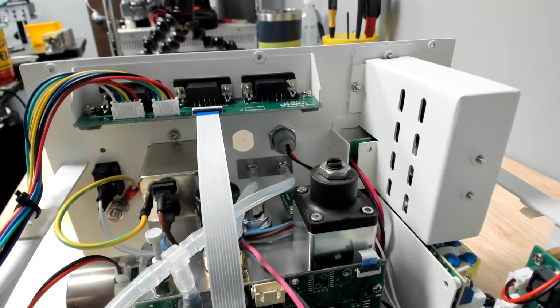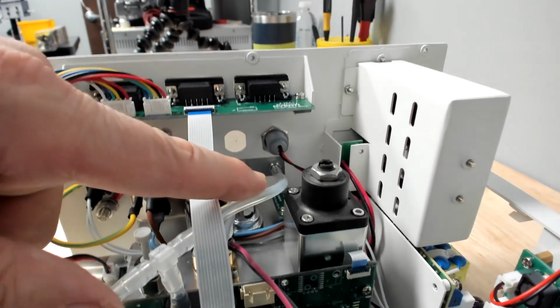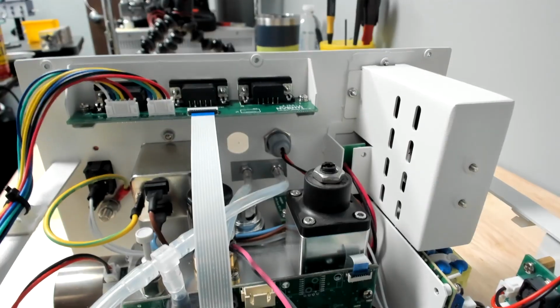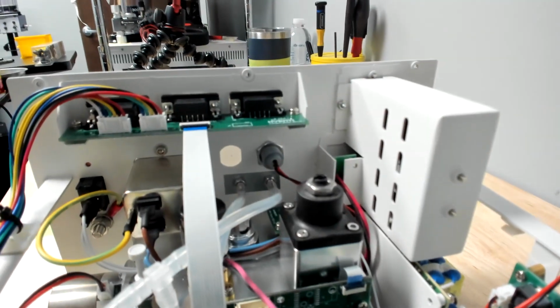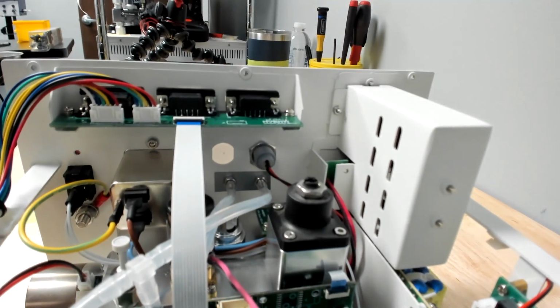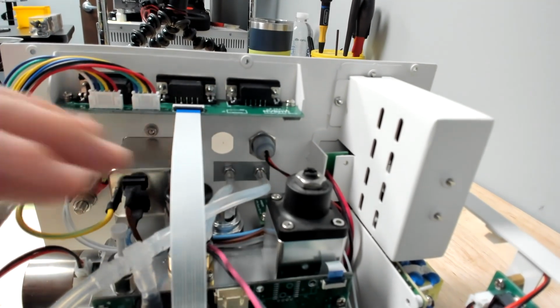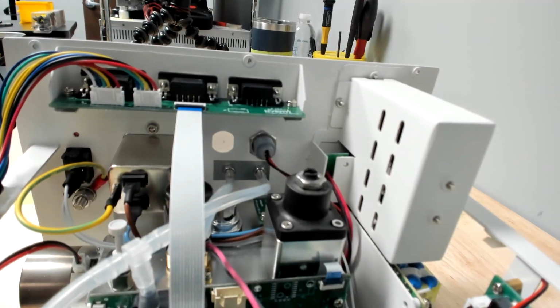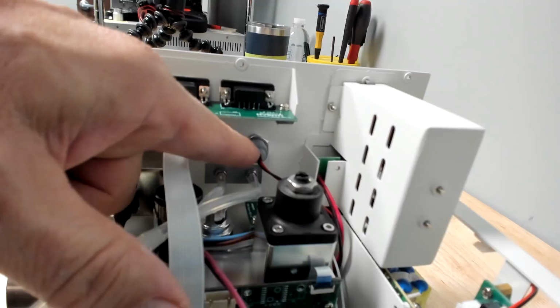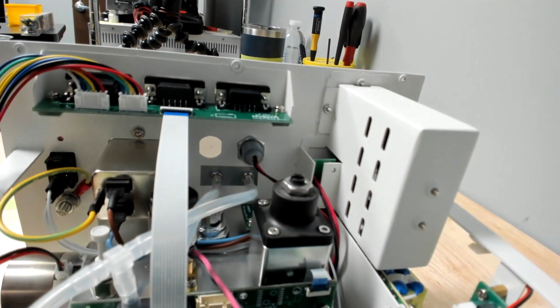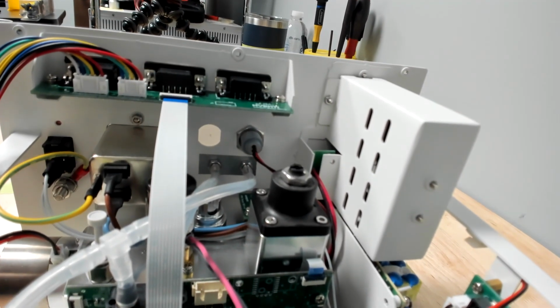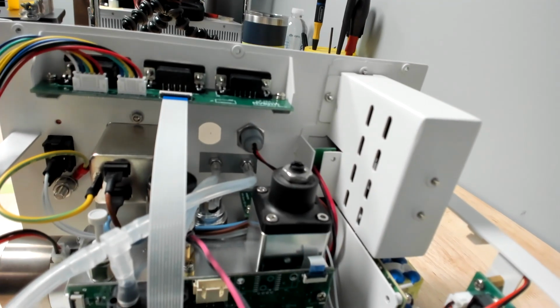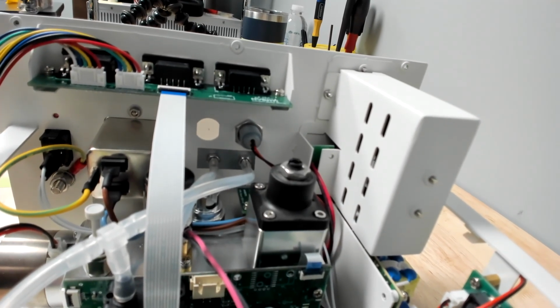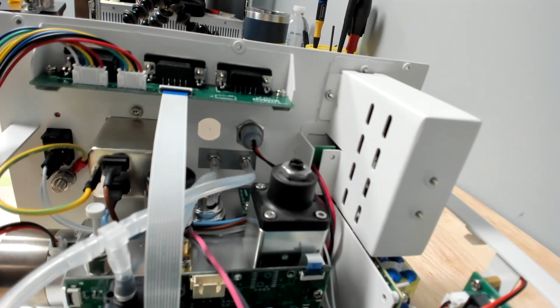So from the inside, we're looking at our 2 ports here. This is our oxygen sensor port. So we want to be careful. There's a lot of cables in here, things that we can break. So I am actually going to remove the O2 cell receptacle here. That'll give us a little bit more room to work on reattaching the sensor ports.